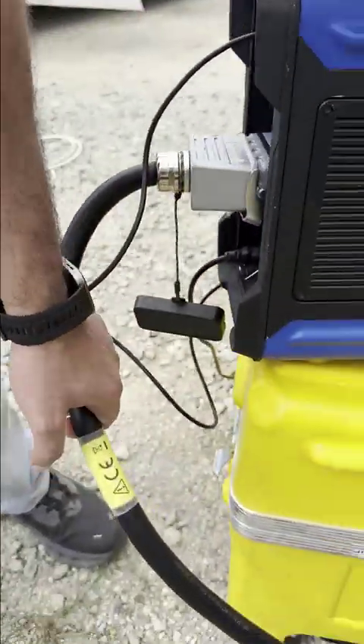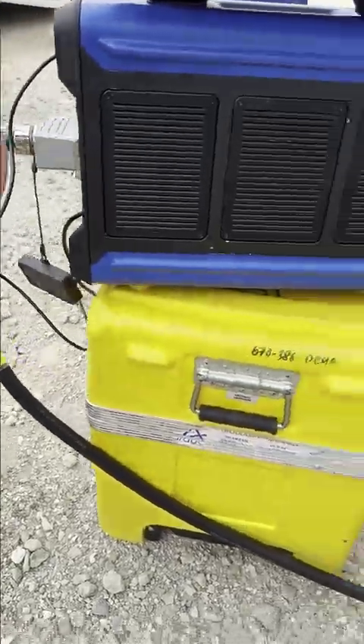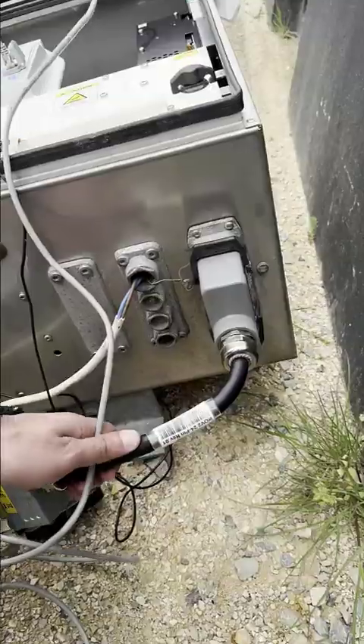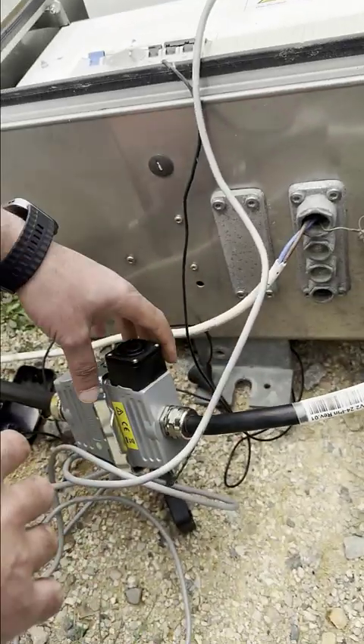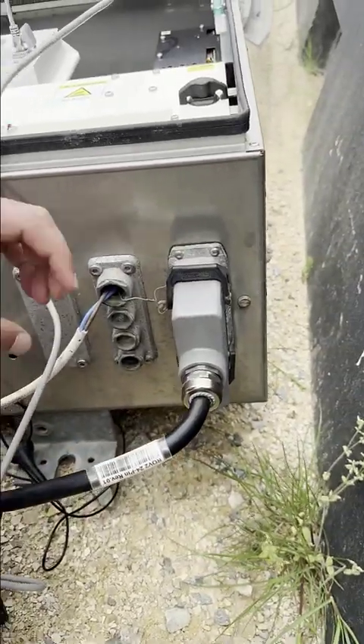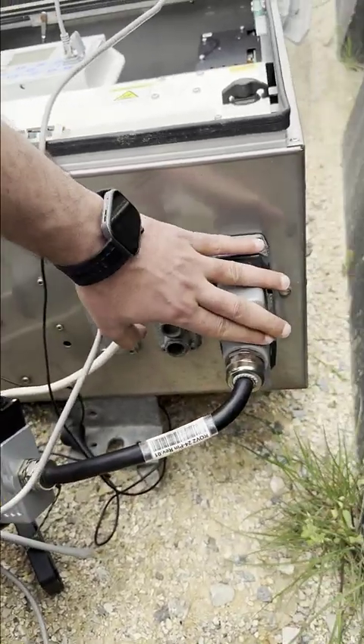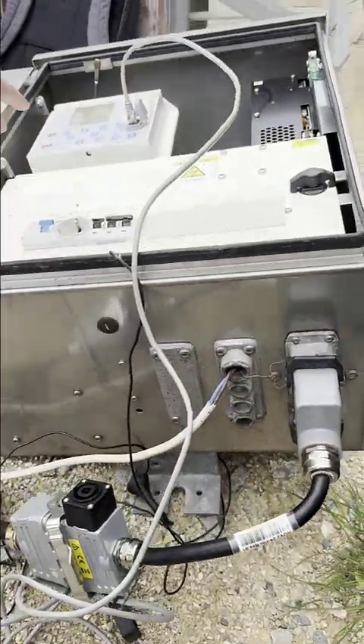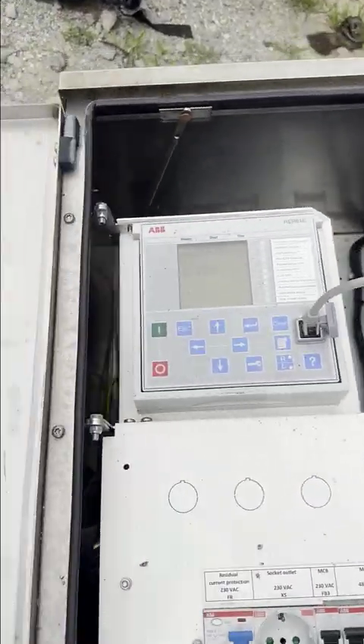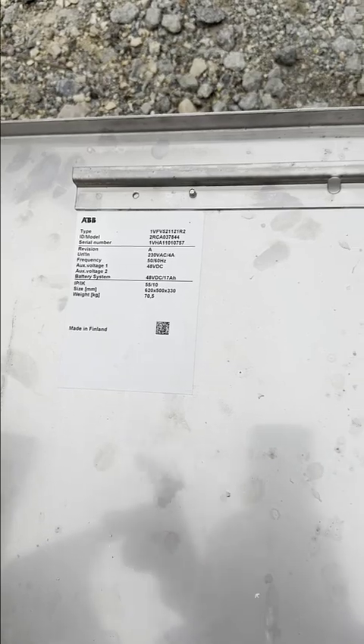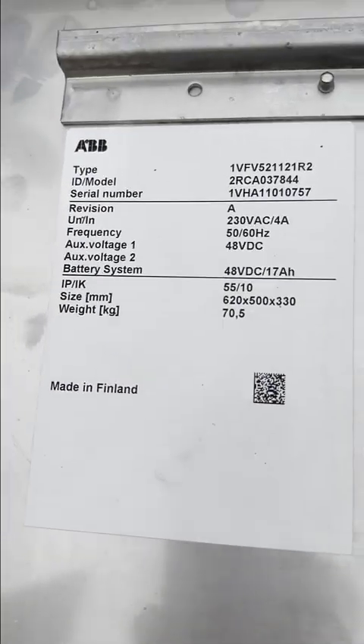Here is the extension cable connected to the safe and touch proof, and then we have here the ROV2, which is our controller adapter. As you can see, it's about 30 centimeter or 40 centimeter. It's connected to the test plug of the protection relay. Here is the nameplate of the protection relay, RER615, and you can see from here the nameplate and the control circuit voltage is about 48 DC voltage, as you can see.